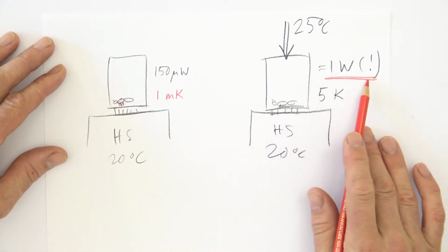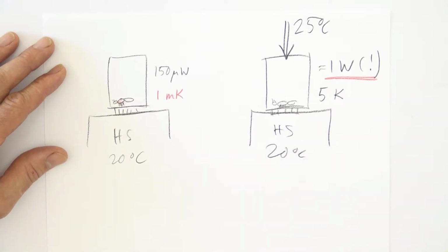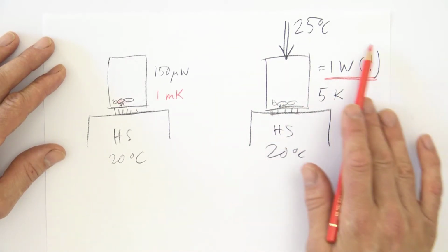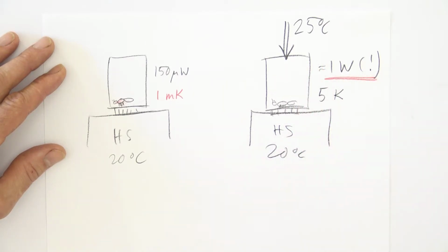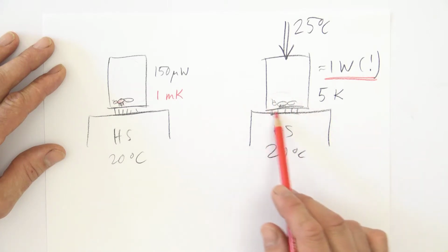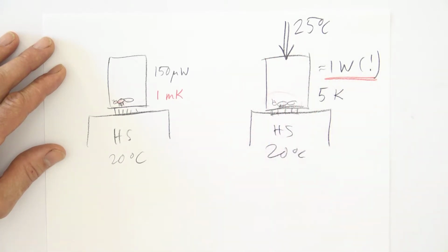This thermal power means that the calorimeter goes far out of range. And this is initial disturbance, and these very high thermal powers and very high signals that we get are not at all caused by the insect. They are caused by the wrong temperature of the vial.